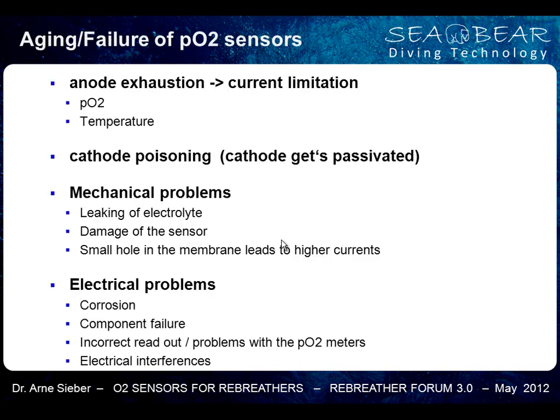So next important point is anode exhaustion, or generally the failures of sensors. Anode exhaustion, a current limitation, is the one we speak about most of the time. Next thing is cathode poisoning. The cathode gets passivated, you get wrong signals. Mechanical problems, leaking of the electrolyte, damage of the sensor. For example, if you have a small hole in the sensor membrane, more oxygen can go in, so you have higher currents. Or electrical problems like corrosion or component failure. Electrical interferences, these are things you have to think about.